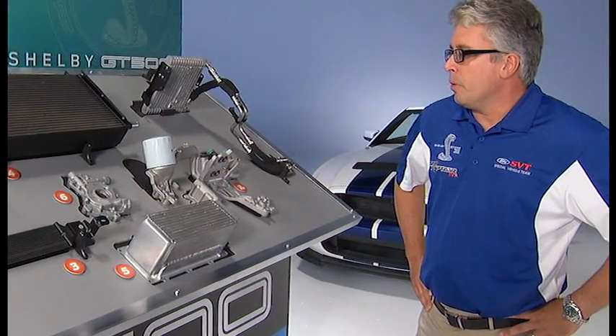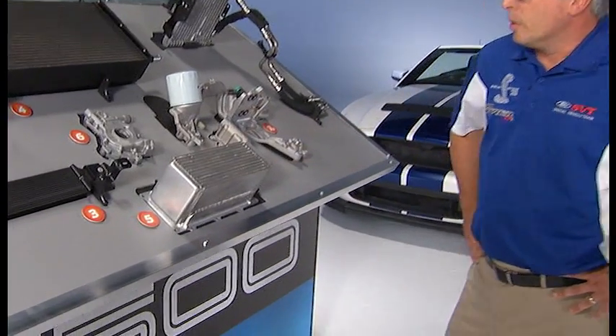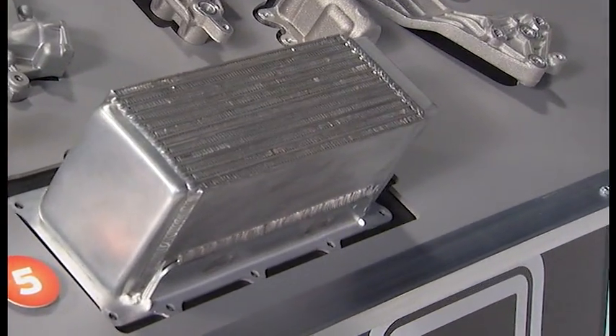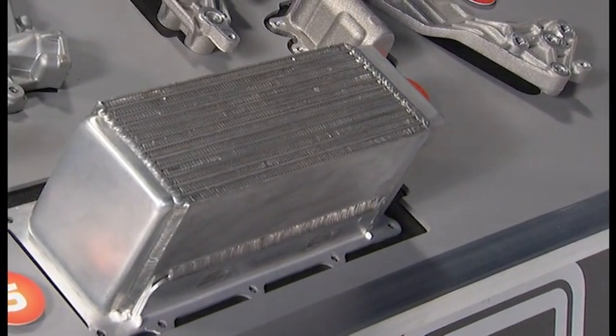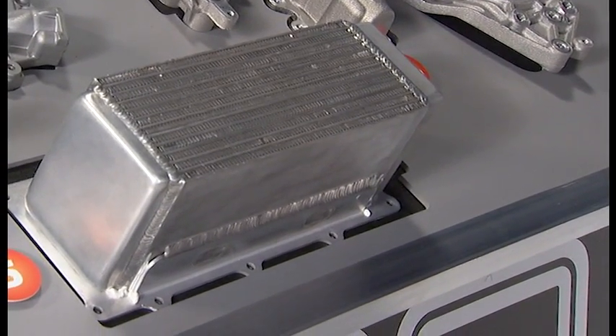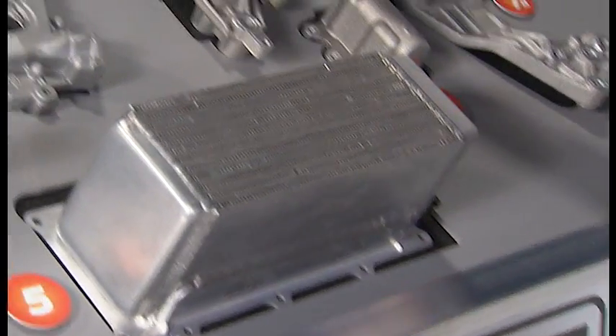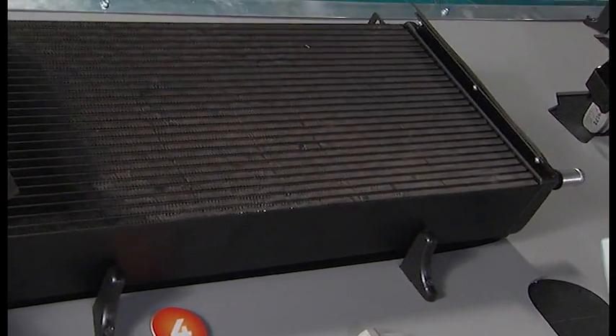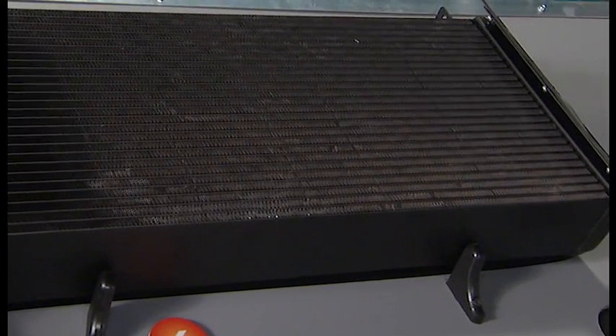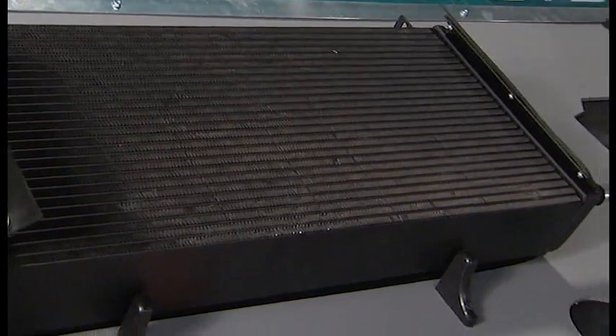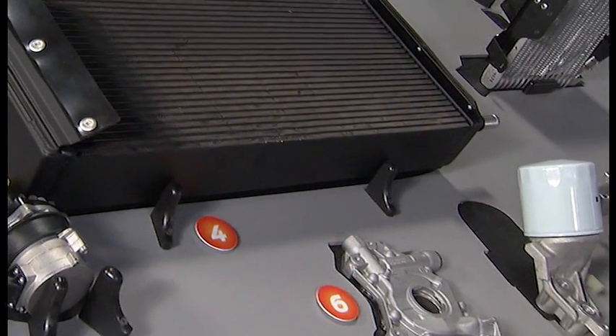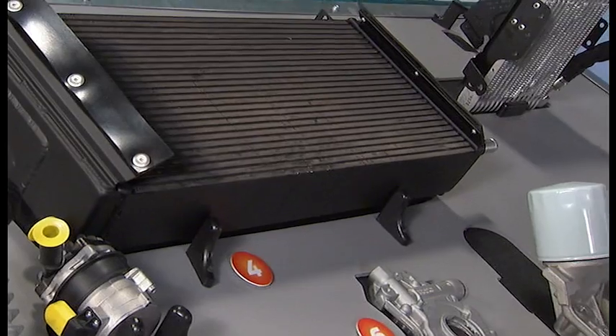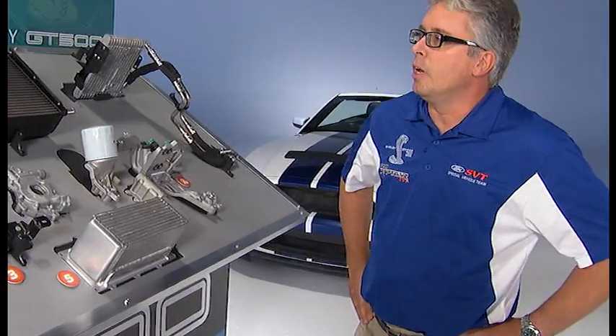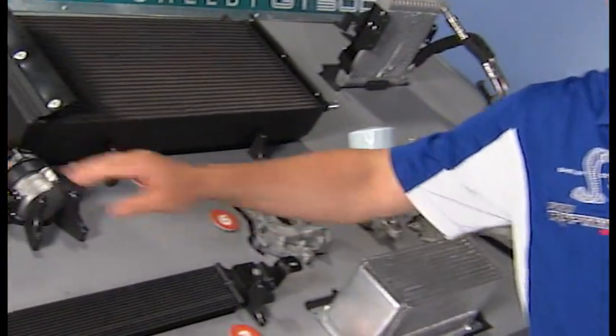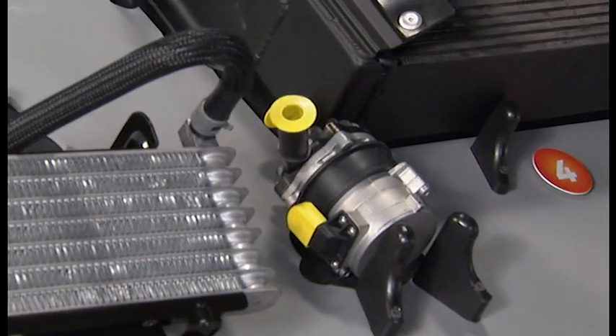We went after every component of the system. With the charge air cooler, we decreased the pressure drop on the air side while also increasing the amount of heat rejection the part was capable of. We did the same with the low temp radiator: it's wider, taller, thicker, bigger in every way, giving more surface area to transfer heat from the coolant into the ambient air. With the increased capacity of both parts, we needed to increase the coolant flow, so we significantly increased the flow rate on the pump to improve overall system performance.